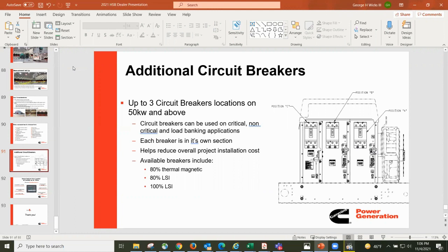So does that inherent design cover what you were discussing earlier, like maybe a computer would shut it down before it overheats, or some kind of internal overload before it even reaches that 800 amp circuit breaker? Yes, you're getting a bit outside my realm, where our industrial guys deal with engineered specs and designs. But I do know both our alternators have thermal shutdowns if they reach a certain threshold, separate from the coolant and engine high temperature shutdown, inside the alternators. And if it's sensing maximum capacity amperage, say a set value of 450 amps, and we're going over that, that could also trigger an overload shutdown. Different genset controls have different shutdowns, and you can add different sensors as optional features and checks.